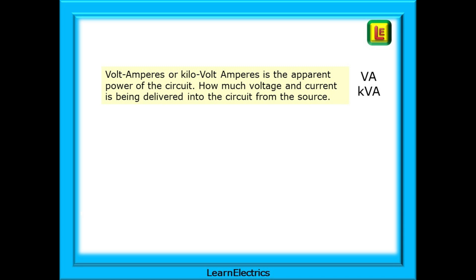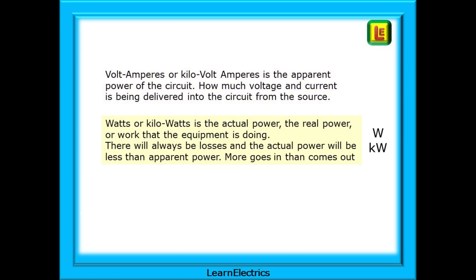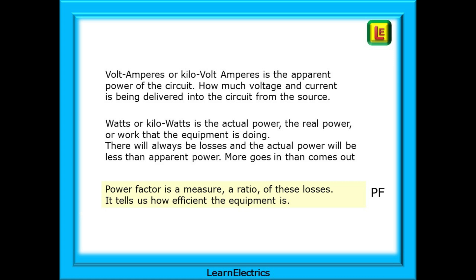Volt amperes or kilovolt amperes is the apparent power of the circuit — how much voltage and current is being delivered into the circuit from the source. Watts or kilowatts is the actual power, the real power or work that the equipment is doing. There will always be losses and the actual power will be less than the apparent power — more goes in than comes out. Power factor is a measure of these losses as a ratio; it tells us how efficient the equipment is. The more efficient the equipment, the higher the power factor. An ideal system will approach but not reach a power factor of 100% or 1. Typically 85–90%, written as 0.85 to 0.9.